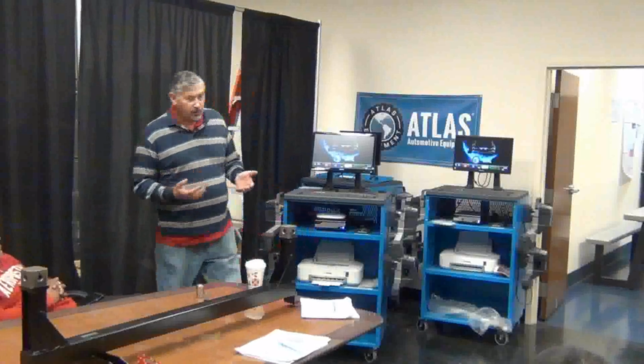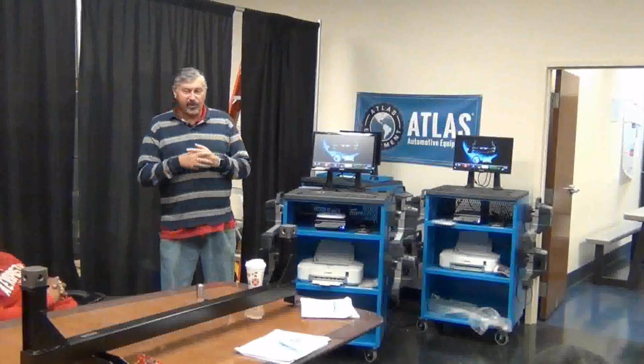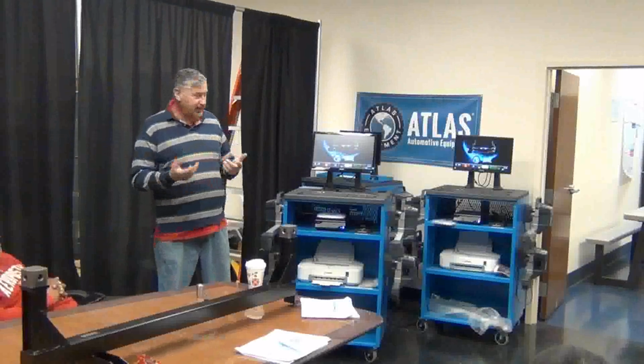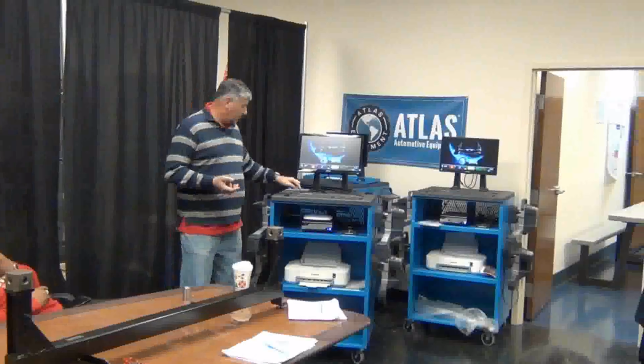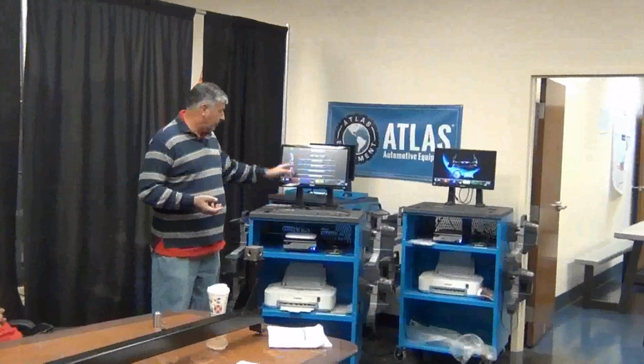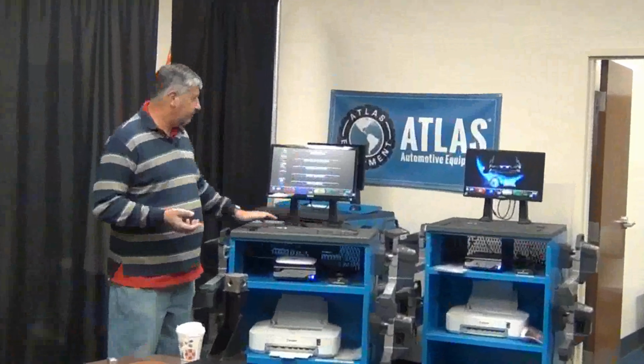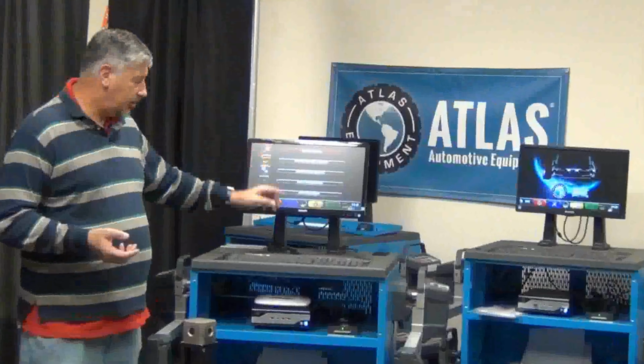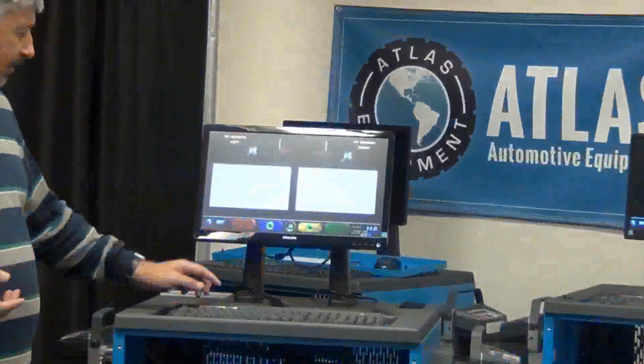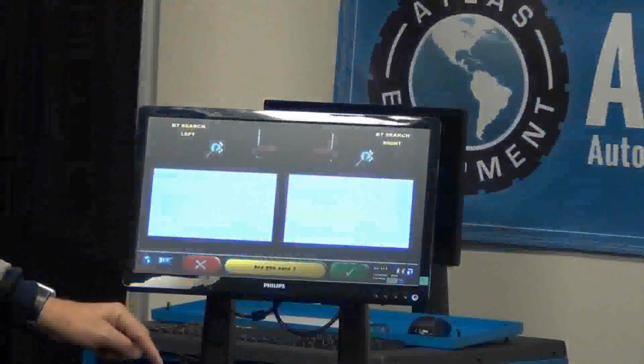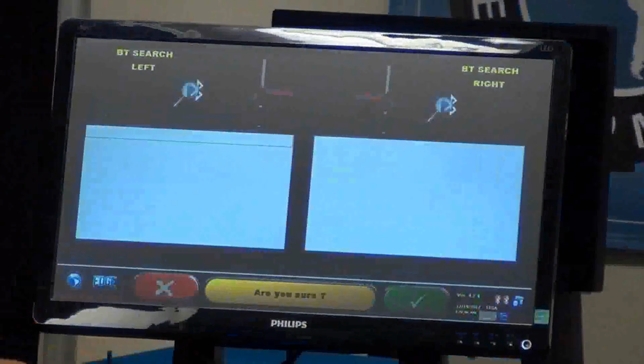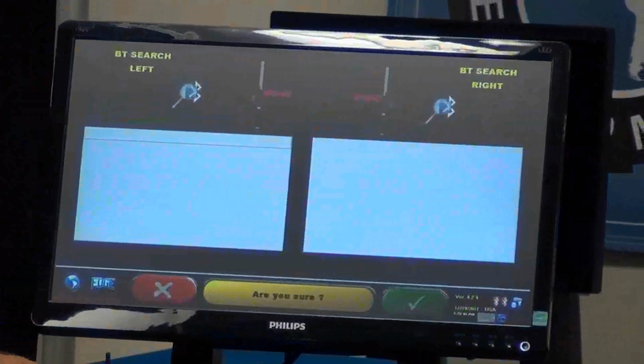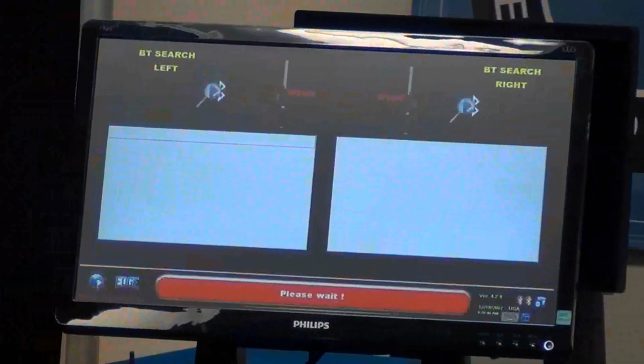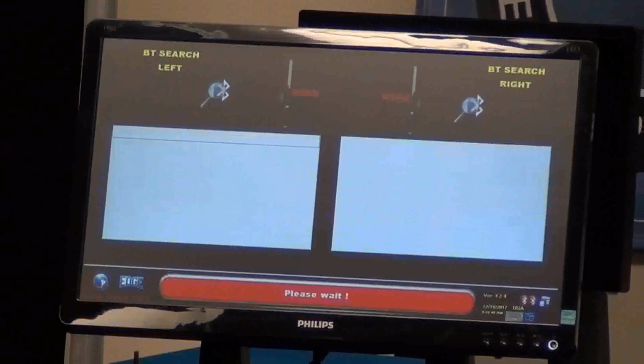Now, the first thing I would recommend you do is verify the Bluetooth connection. You do that by pushing the blue button. You go to System Configuration. You go to Bluetooth Search. Okay, and of course you push the F5. I repeat, you push the F5 button, or the black button. Then the green one, which is the F4 button, and then ensure that your sensors are switched on.